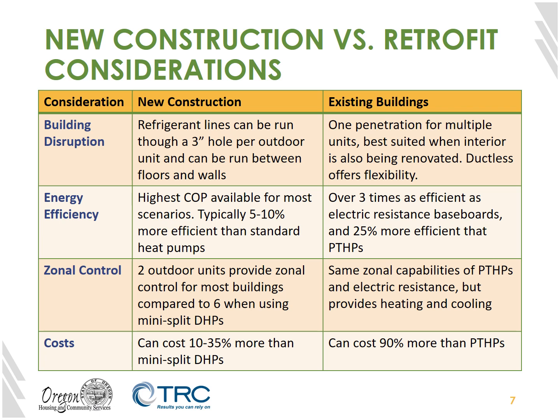When we talk about zonal control, if we're looking at a VRF system and we're designing new construction, we could have as little as 2 outdoor units providing zonal control for most of the different multifamily buildings that are being newly built. That's really terrific to think about, only those 2 outdoor units, both in terms of price and use of space on the exterior. To do the same number of indoor units with a mini-split system, you would have to use at least 6 outdoor units. So triple, in this case, the number of outdoor units.